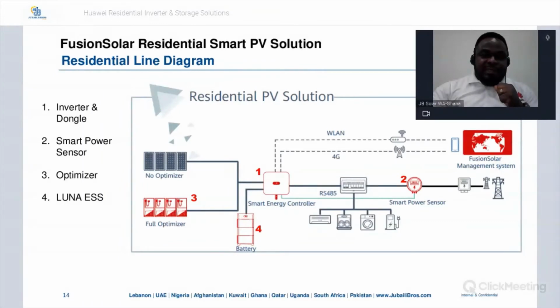So this is the Huawei inverter, and connected to it is a smart dongle for communication, that's the communication device under the inverter. Then we have the smart power sensor, basically a power meter. Most of our power meters are bi-directional smart power meters also distributed by Huawei. This enables production measurement and zero export functionality, which I'm sure each of us knows about.